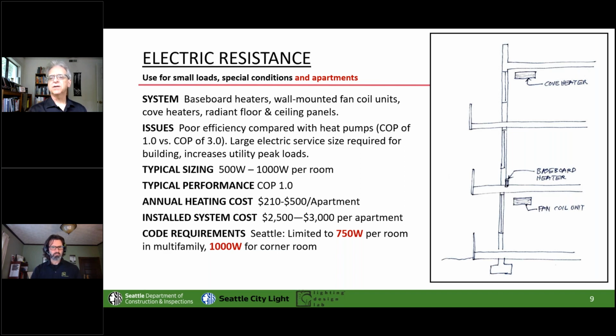We actually started with 500 watts per room, and then some affordable housing provider called up and said, can we make it 600 so that if we're over a garage or something, we can have a little extra allowance for that loss through the floor? And then somebody said, you know, most product types don't go any smaller than 750 watts. So let's do that, and we'll do 1,000 for a corner room. It's obviously cheap, obviously easy. That cove heater at the top seems to be the more popular version of this these days. It stays out of the way of your furniture and provides some, I guess, some radiant heat. So that is your option if you don't want to put in a heat pump.